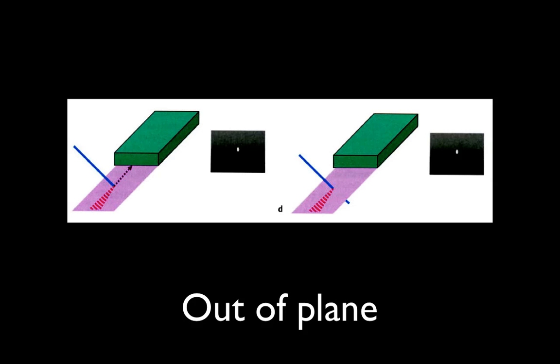Now the problem with out of plane approach is that if the needle tip is just perfectly in the beam, the tip of the needle is just in the beam, you get a signal like you see on the left hand side. You get a bright white dot. Now the problem is that if your needle is 3 inches through the beam, you will get the same signal. So you cannot keep your probe still and expect to get an accurate idea of where the tip of the needle is.